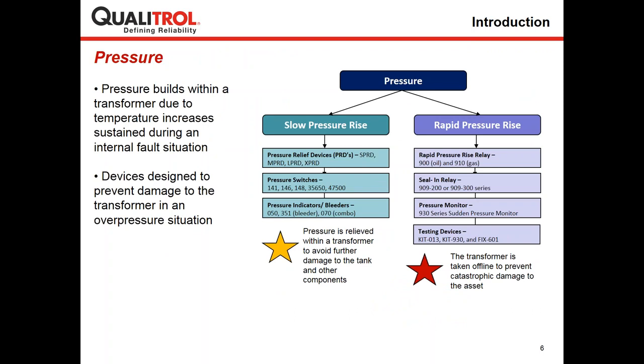Now, pressure builds up on your transformer when temperature increases, and this can be a result of an internal fault scenario. Therefore, we have devices that are there to prevent damage to your assets in that type of overpressure situation. There are 2 main types of pressure that can be present. You have slow pressure and you have rapid pressure. We offer devices for both of those instances. Some people may be familiar if we look at the slow pressure side with our small, medium, large, and extra large pressure relief device.